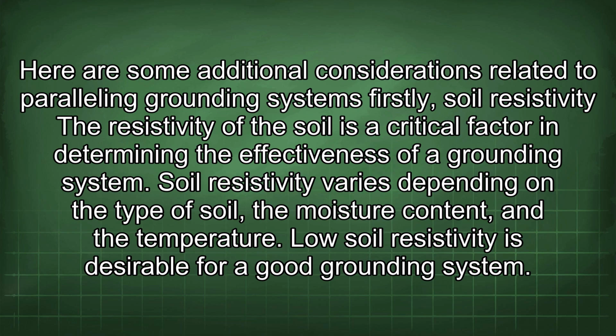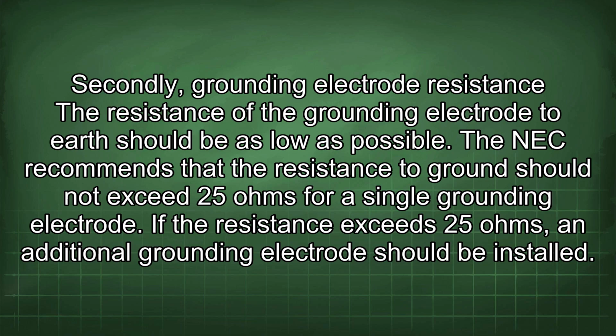Here are some additional considerations related to parallel grounding systems. Firstly, soil resistivity. The resistivity of the soil is a critical factor in determining the effectiveness of a grounding system. Soil resistivity varies depending on the type of soil, the moisture content, and the temperature. Low soil resistivity is desirable for a good grounding system. Secondly, grounding electrode resistance. The resistance of the grounding electrode to earth should be as low as possible. The NEC recommends that the resistance to ground should not exceed 25 ohms for a single grounding electrode. If the resistance exceeds 25 ohms, an additional grounding electrode should be installed.